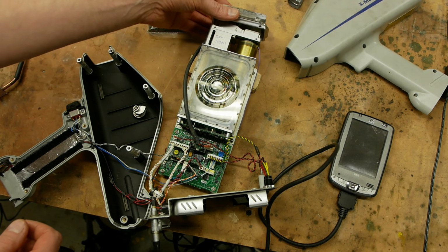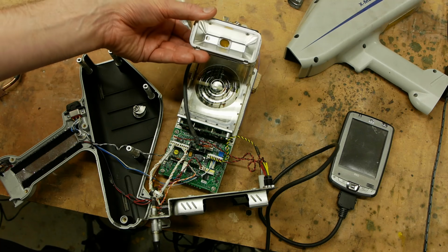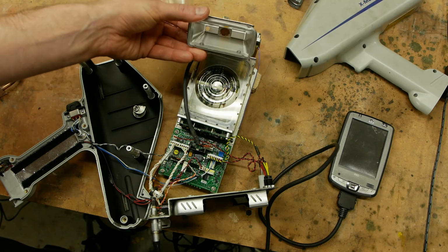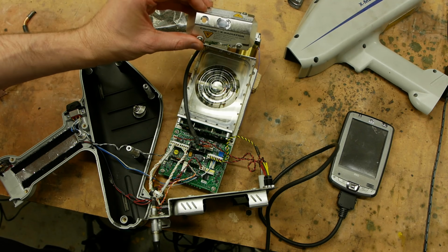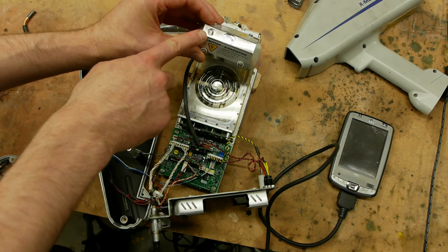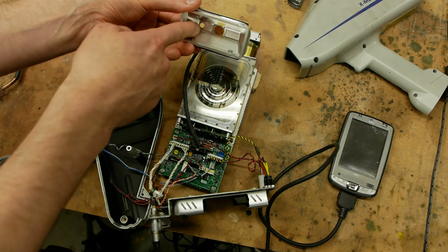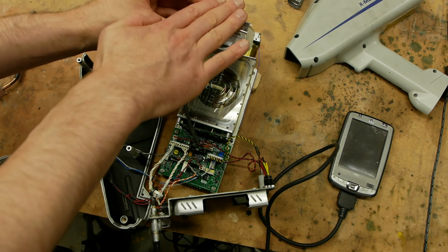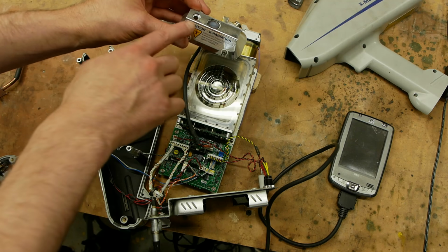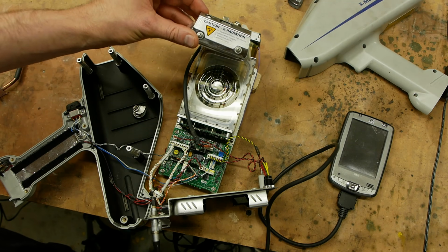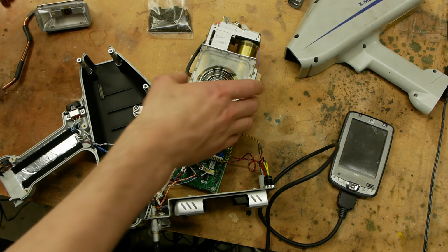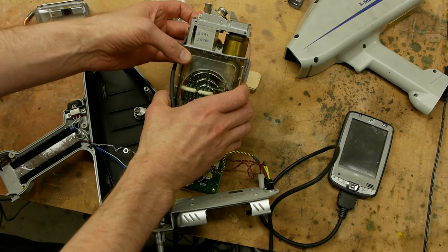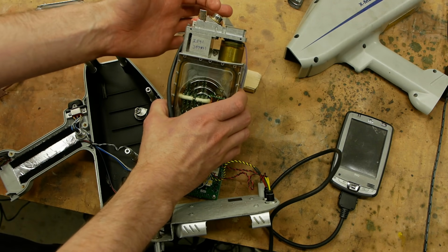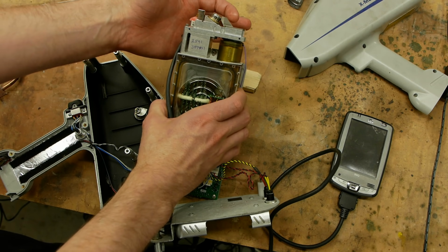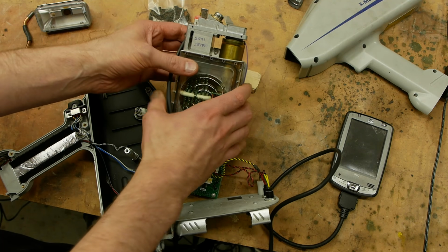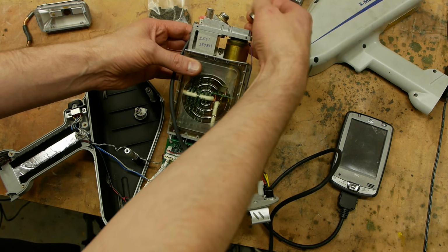And then there's a snout here that just protects the stuff that's underneath it. I don't think that filter does much but keep dirt out. And remember, this is for the proximity sensor, so there's just an optical sensor in there. Unless there's something opaque pushed up against the front of this, it won't activate the X-ray tube. And then we can see that there's definitely two things going on here. This is the sensor, and this is the X-ray emitter side. And we can pull that off.